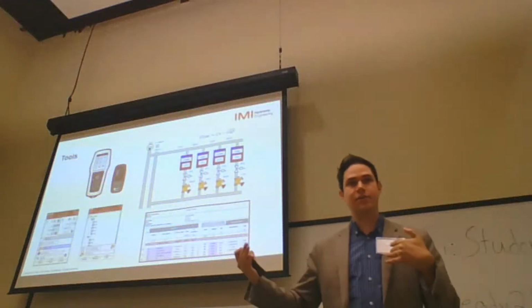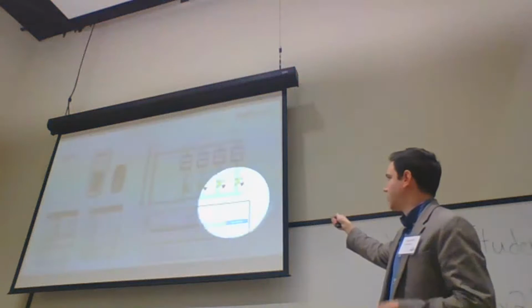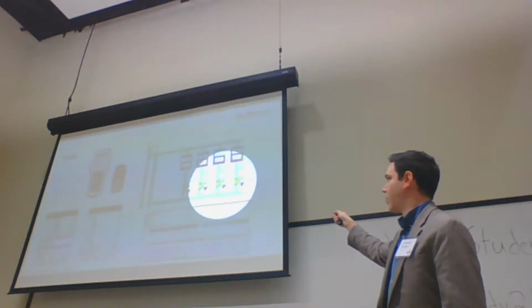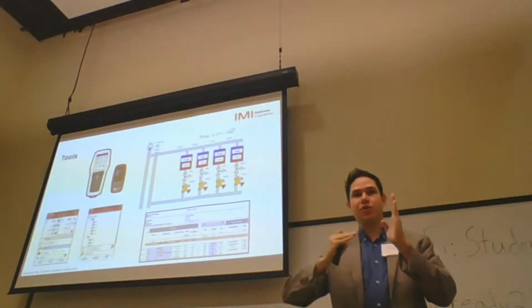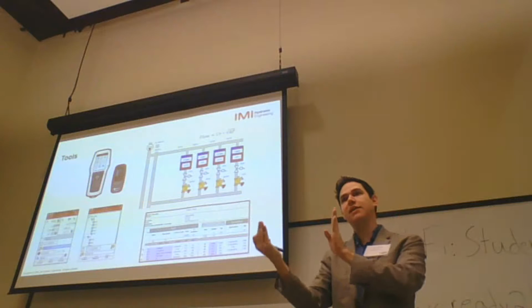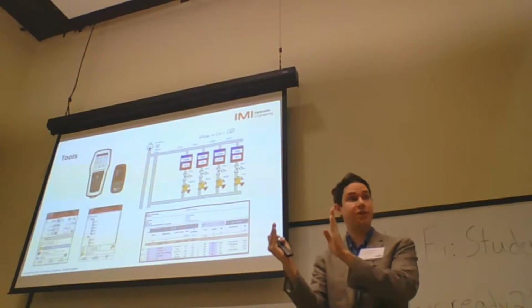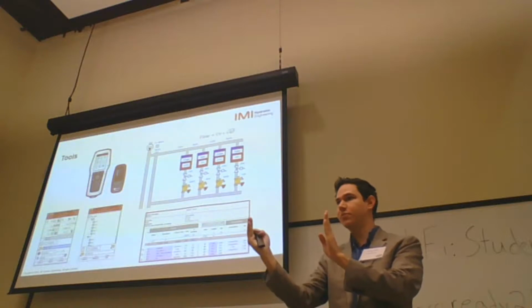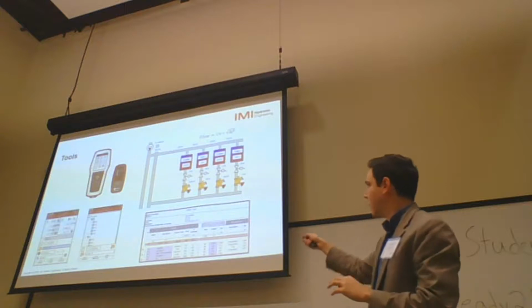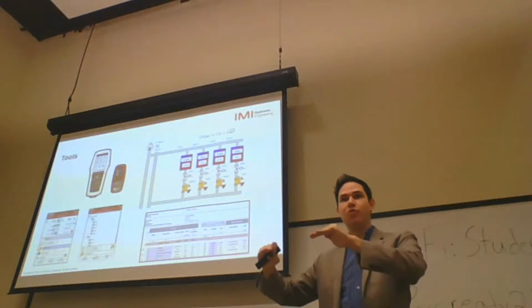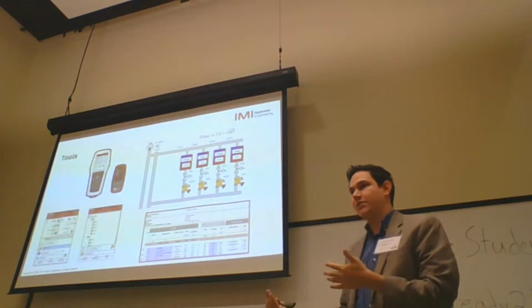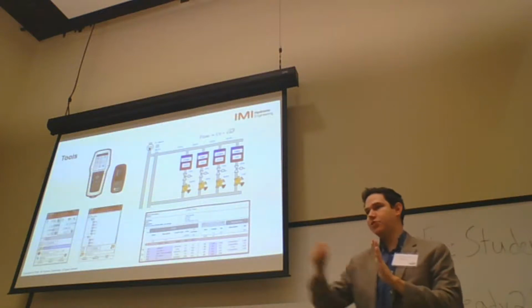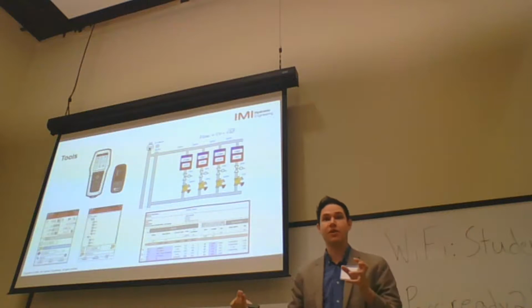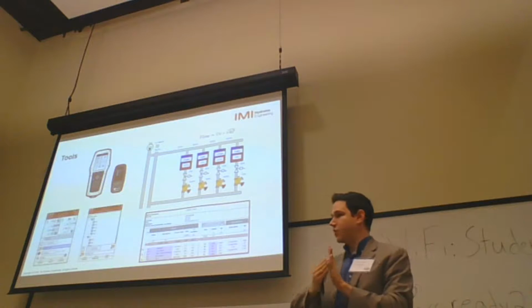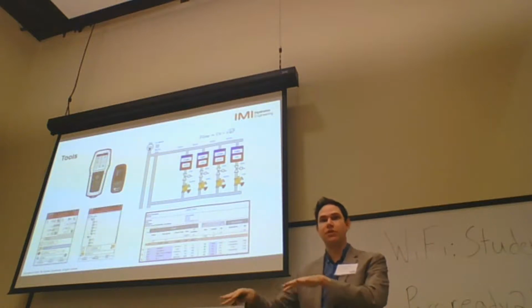And the methodology behind this software is that you always start measuring on your last coil and you measure with the one before. When you match the same percentage between your last coil and the one before, they are balanced between each other. It doesn't matter if it's exactly 100% of the flow, but if it's 120%, 20% overflow, and 120% overflow, as soon as you move the one valve before, the 2 valves at the end will move proportionally up and down. So what that means is what we call the proportional rule. Everything upstream, the change that you're making on the system, that could be a balancing valve in this case, everything upstream will move at the same proportion if they were set before.